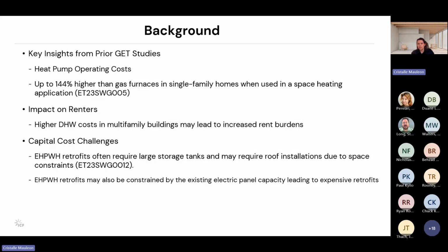In multifamily buildings, higher operating costs are often passed on to renters, many of whom are already cost burdened, so we wanted to investigate the costs. The second study focused on GAHP sizing and design, and in the process of investigating design requirements for gas heat pumps, we also found that electric heat pump water heater retrofits typically require large storage tanks, which many existing mechanical rooms cannot accommodate, which can lead to costly roof installations.